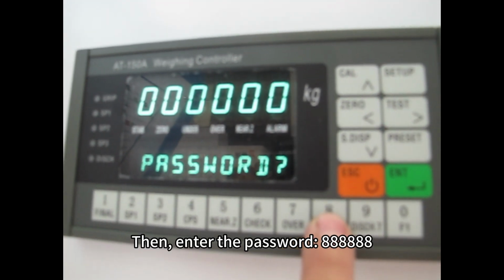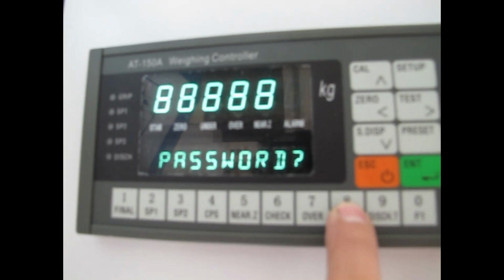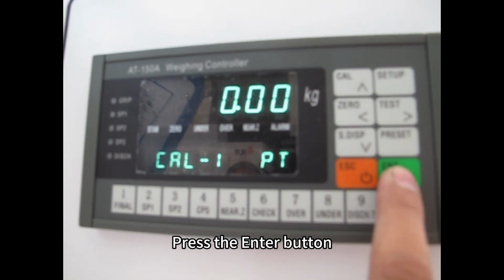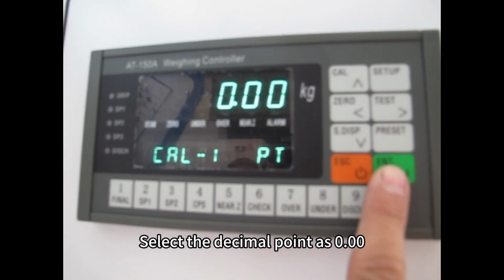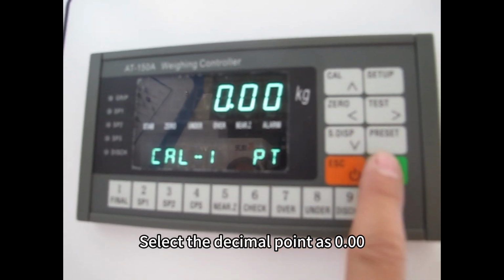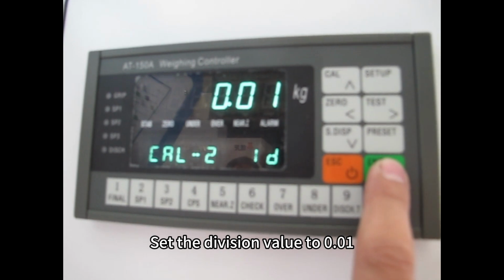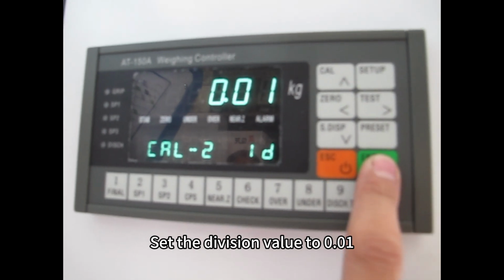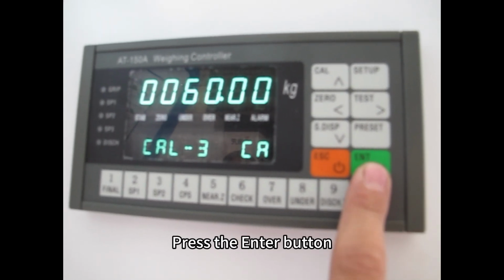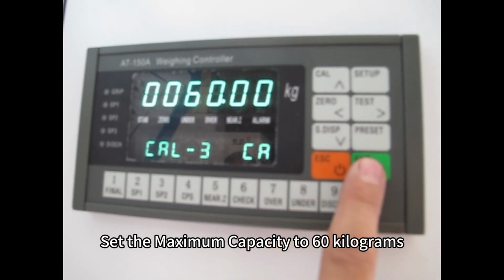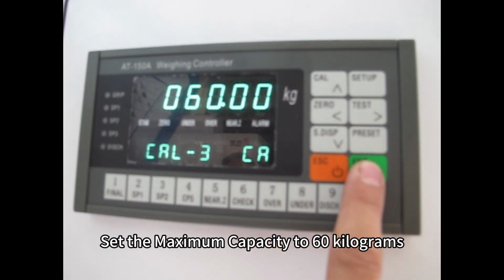Then, enter the password: 888888. Press the Enter button. Select the decimal point as 0.00. Set the division value to 0.01. Press the Enter button. Set the maximum capacity to 60 kg.